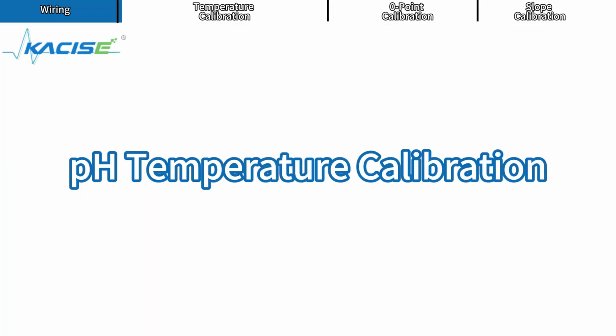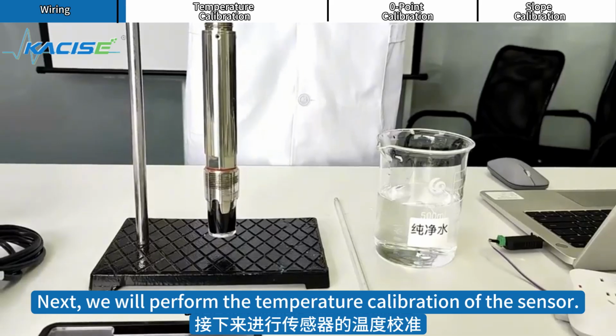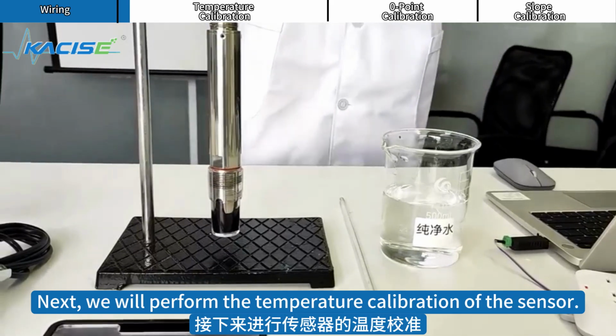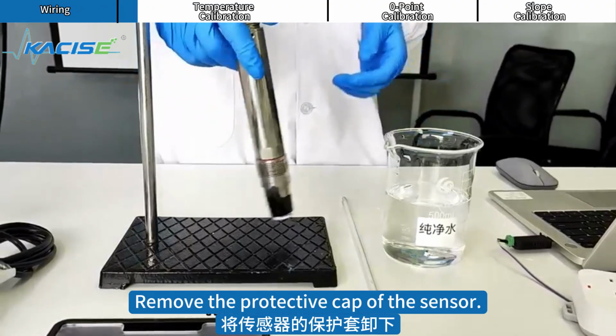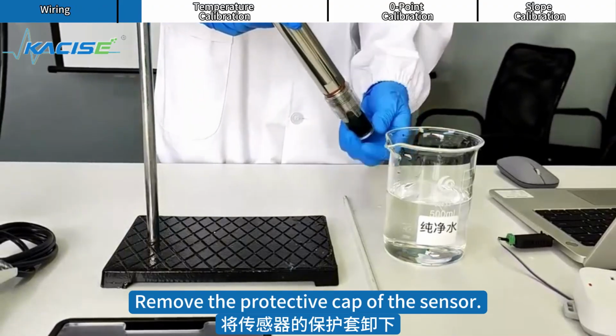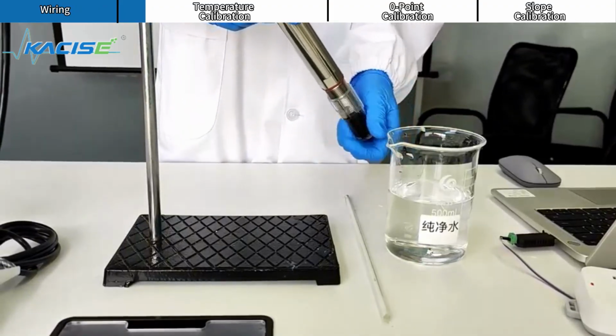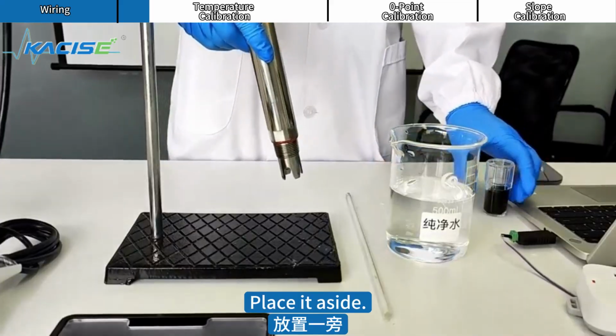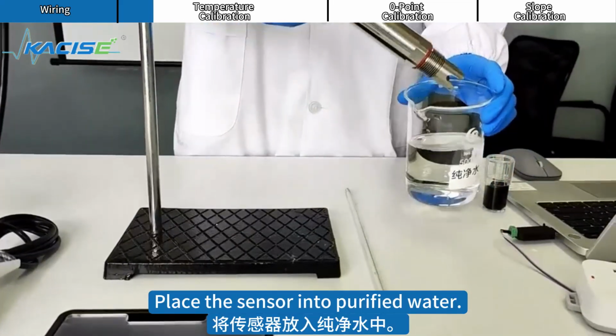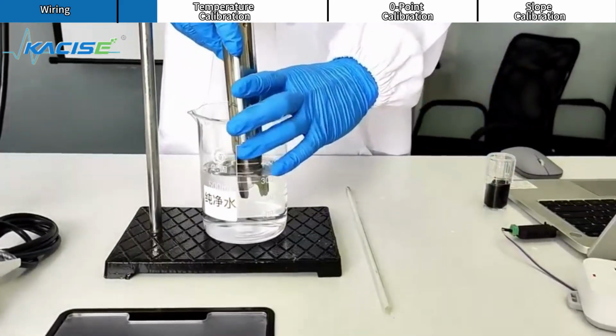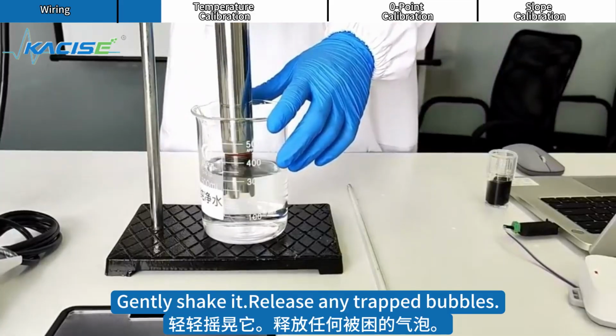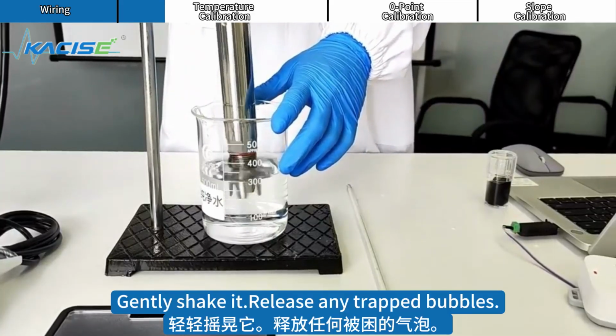pH temperature calibration. Next, we will perform the temperature calibration of the sensor. Remove the protective cap of the sensor. Place it aside. Place the sensor into purified water. Gently shake it. Release any trapped bubbles.